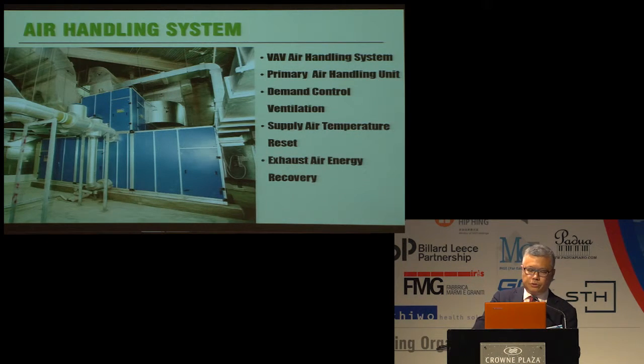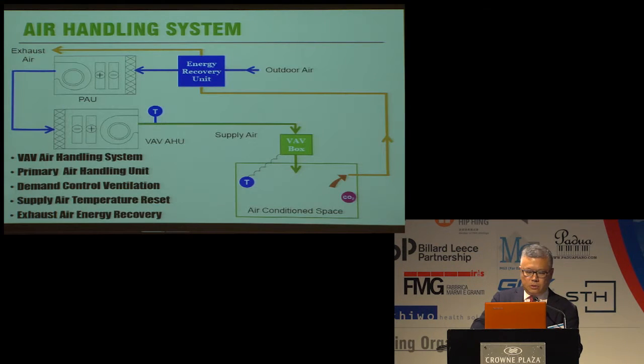Multi-zone VAV air handling systems are normally used together with the primary air handling systems for hospitals. The cooling and dehumidification of the internal space are normally done by the AHU, while the cooling and dehumidification of the outside air is handled by the primary air units. Demand control ventilation strategy using CO2 sensors to control the outside air supply rates can be adopted for large spaces that are densely populated, but with a widely varying pattern of occupancy, such as open plan office and also conference room. And supply air temperature reset during non-peak weather months and also unoccupied period can substantially reduce the air conditioning load.